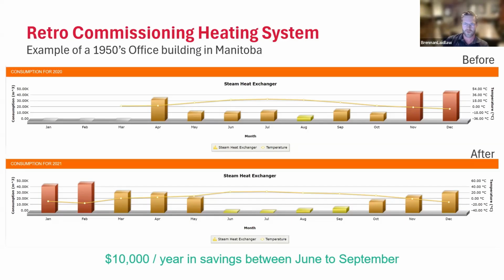The solution was it was actually running too much, and it was constantly running and generating heat in the rest of the building. So we put in an optimization program where we changed the sequence of operations. And the next year, running the same analytics, we saw a definite decrease in energy usage in the summer, and that amounted to about $10,000 a year in savings just on this measure alone, because it was such a large building. And you know what? Don't simultaneously heat and cool.